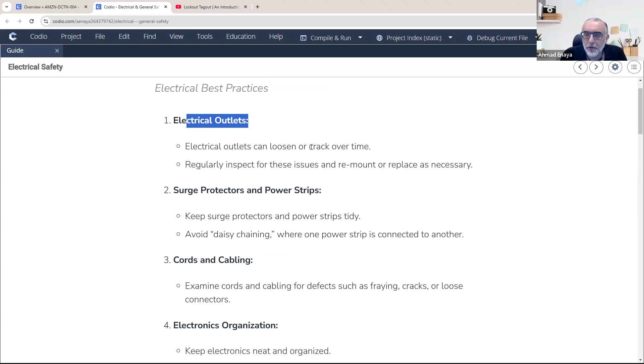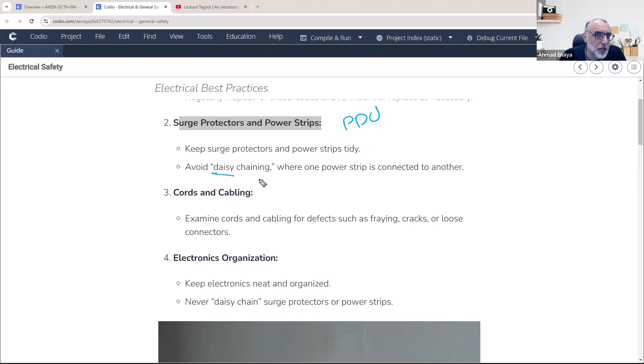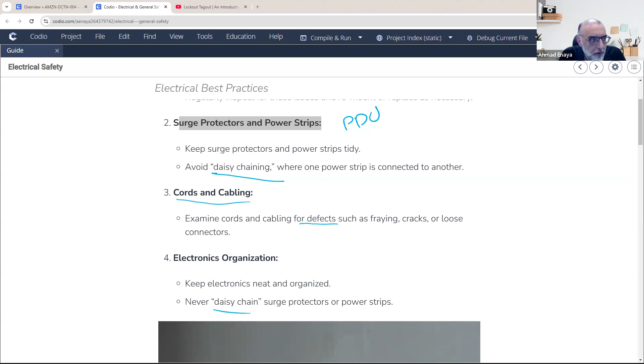Inspect surge protectors and power strips, also called power distribution units, or PDUs—we'll talk about PDUs later in this course. Make sure they are tidy and never daisy-chained; all power strips and PDUs should connect directly to the source. If you have power cords or cables, check for defects like cracks or loose connectors, and keep electrical systems organized. Never daisy chain one to another.